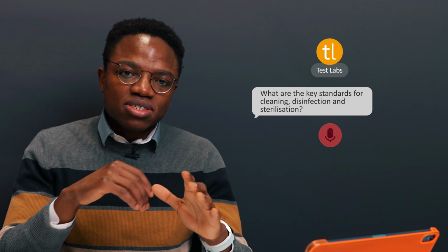As for the next question, what are the key standards for cleaning, disinfection, and sterilization? So all standards are just a way for us to standardize testing across the entire industry so that all the evidence that's provided to the notified bodies and the regulators, it's all sort of following the same framework. For reusable devices, the guidance starts with a standard called 17664-1 for critical devices and -2 for non-critical devices. That standard explains to you exactly what needs to go in your IFU if your device is reusable. It also tells you exactly which standards to employ to validate those claims for your cleaning, your disinfection, and your sterilization.